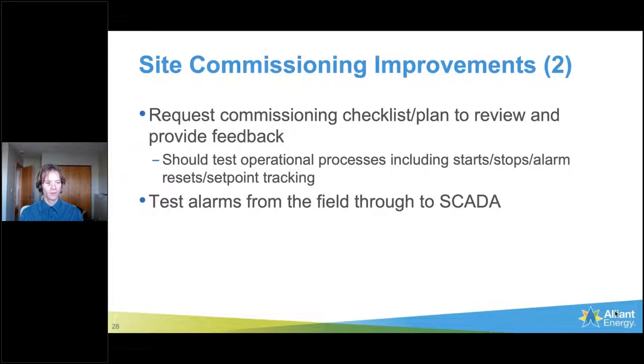This also relates to the concern about wrong registers. Testing the alarms from the field all the way through to the SCADA system is really important—as much as you can do that, since some of these are internal alarms to the BMS and might be difficult to simulate.